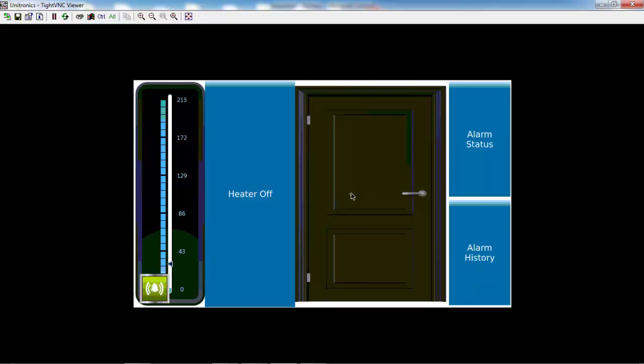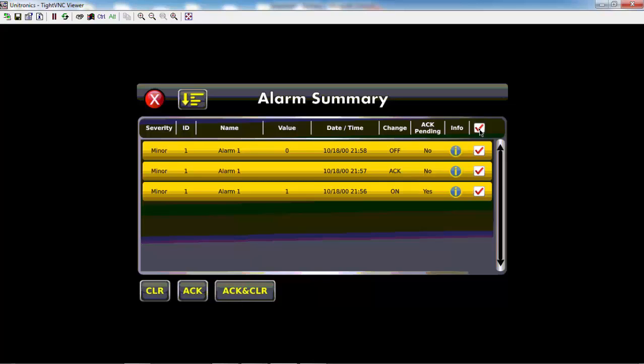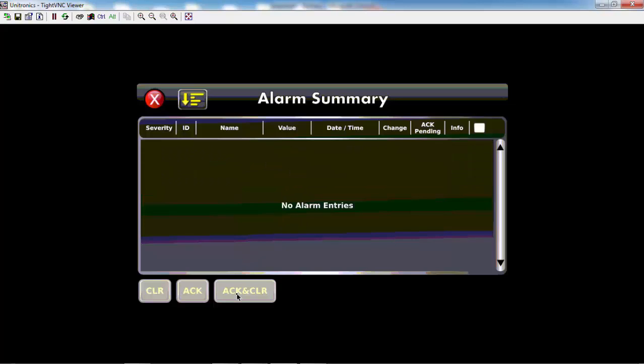Now the alarm banner has been minimized to the small alarm button. And if I would like to clear the alarm summary list, I can click on this button. And by using the top row checkbox, select all of the listed alarms and acknowledge and clear. Now you can see that the alarm list is empty. The alarm summary list has a maximum of 1,024 rows.